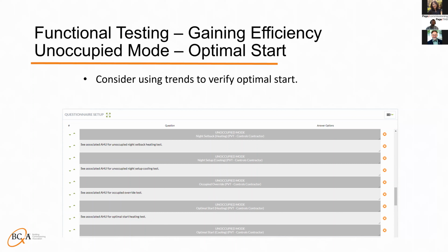Optimal start. One fast way to test optimal start is just by looking at the trends. Sometimes in Texas, all you need is 1 week worth of trending and you will be able to see morning warm up and cool down.